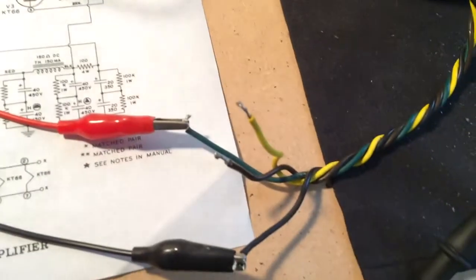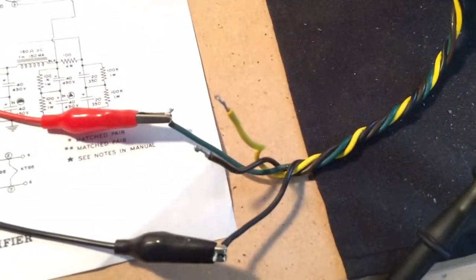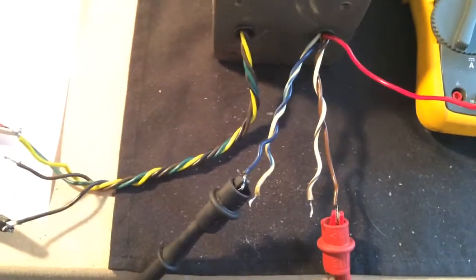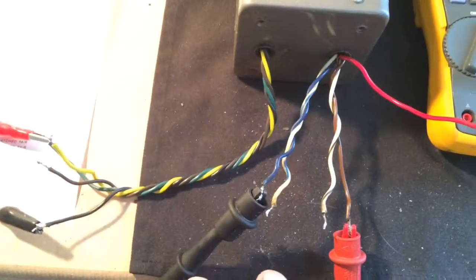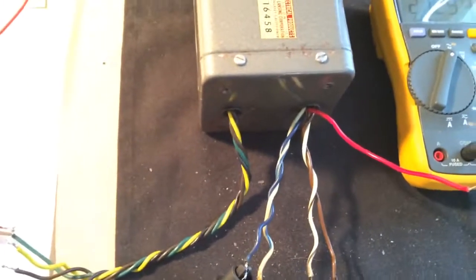I'm going to go through the three output colors and we'll just fill in my chart and look at the consistency. So this is 0.9 volts AC going through the secondary and then I'm measuring on the brown and blue wires on the primary. We've got 21.26 volts.